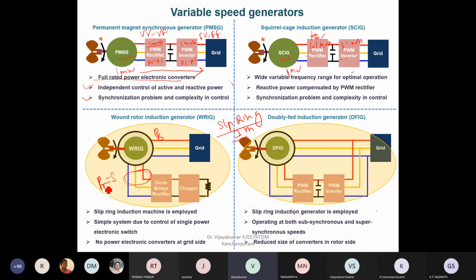Your rotor power is slip times your stator power. So you get the slip power at the rotor. Suppose my machine is operating in a 20% slip range. If I say it's a 1 MVA machine, then only 200 kVA, or 200 kilowatt, is the maximum available at the rotor terminals.